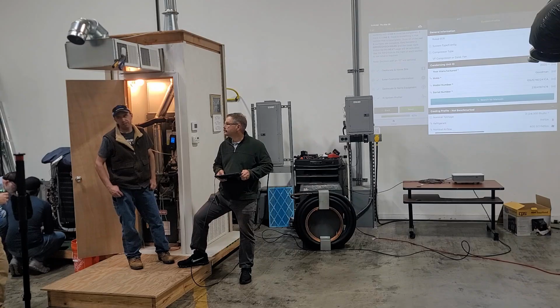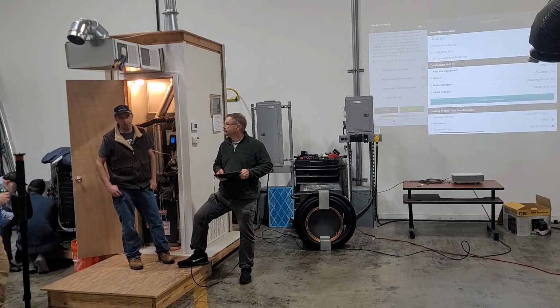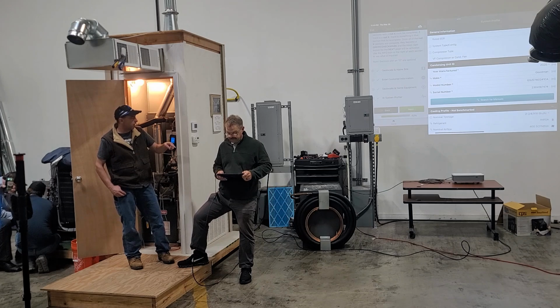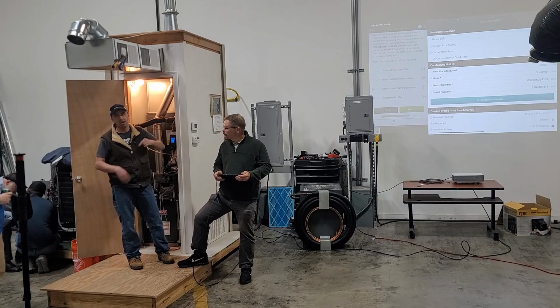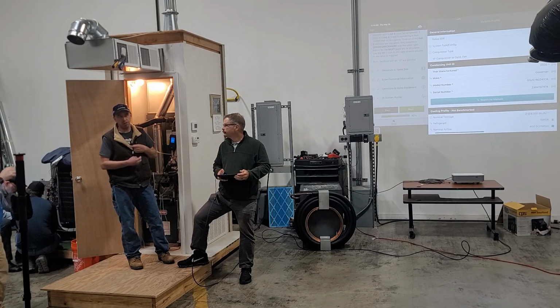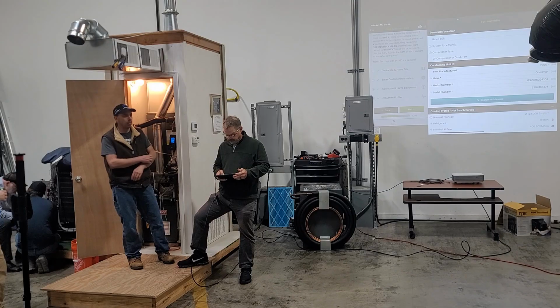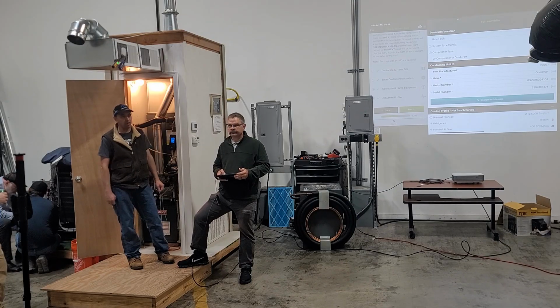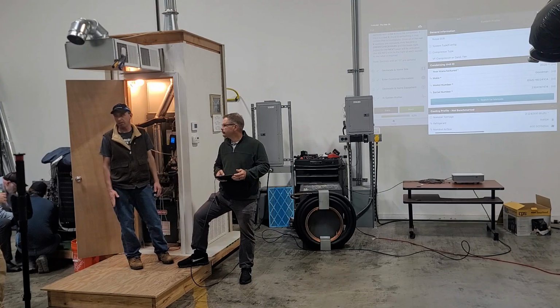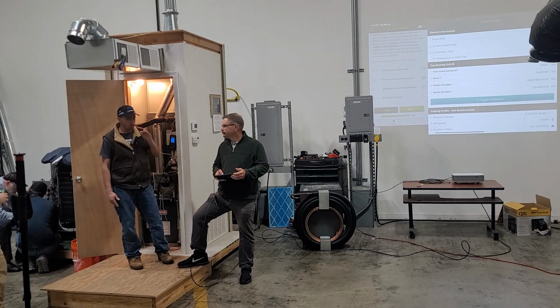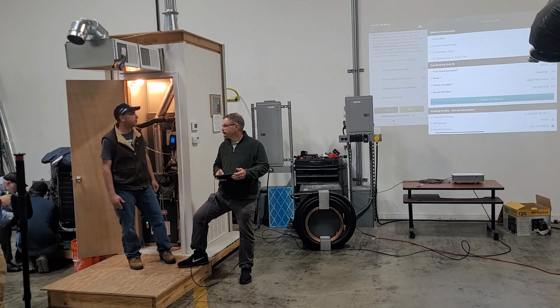When you're working on a modulating system, whether it's an air conditioner, heat pump, or furnace, you're going to run it in test mode or charge mode, full blast, okay? So even if you check the little box here that says variable frequency compressor or condenser, all that's doing is changing the power factor target for the electrical measurements. Because being a variable frequency drive, it does not have as high a power factor as a PSC motor. So that's all that box does. That does not tell MeasureQuick that it's a modulating system, and then MeasureQuick can magically anticipate what that modulating system is trying to do. That's not how that works. You need to have it in test mode, full blast, steady state.